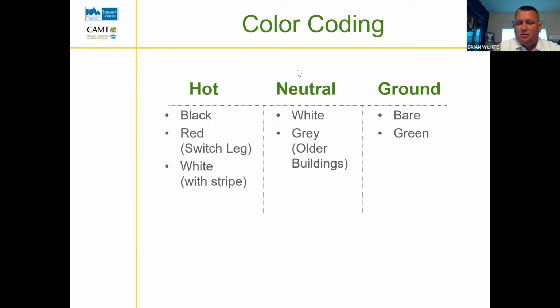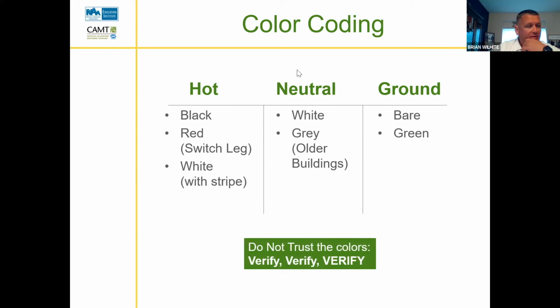When we get into our 24 volt, our secondary voltages, these rules don't apply. And so when we look at our thermostat, for example, it has a green wire in there, and that green does not mean ground. So this only applies in our primary forms of electricity. However, we cannot trust. Again, we have to verify using our multimeter.